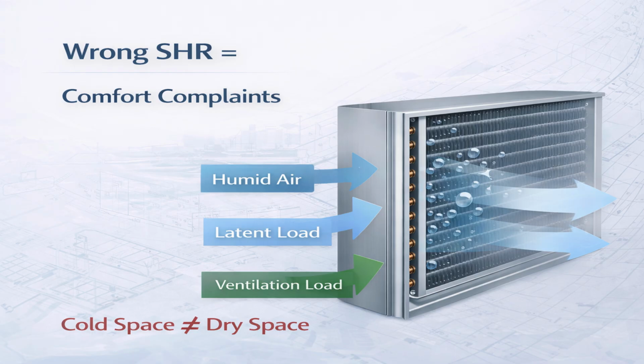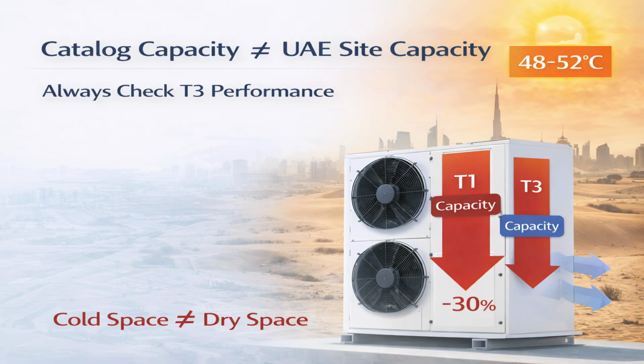This is why SHR alignment is critical, and why many systems fail even though the total load calculation appears correct. When we look at HVAC catalog data, most performance ratings are given at what is known as T1 conditions. T1 represents moderate outdoor temperatures and controlled indoor conditions. These ratings are useful for comparison, but they do not represent how systems actually operate in hot climates.